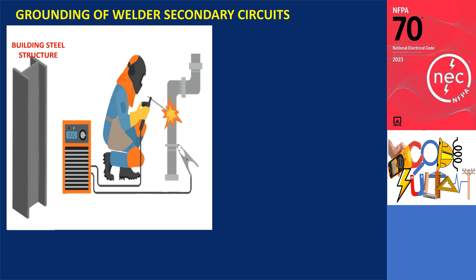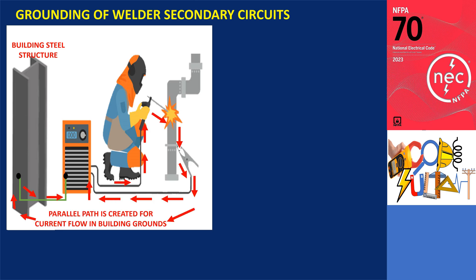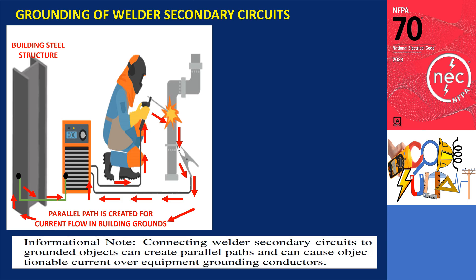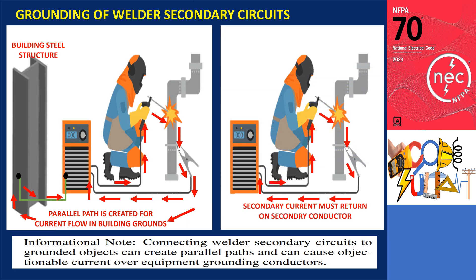Another situation where objectionable currents may arise is when the secondary circuits of a welder are connected to grounded objects. This connection can create parallel paths, resulting in objectionable currents flowing through equipment grounding conductors. This example is mentioned in the informational note of section 630.15, which pertains to the grounding of welder's secondary circuits. It is important to note that separately derived systems are not included in this scenario. To prevent objectionable currents, it is recommended to connect the workpiece terminal of the welder to the workpiece or workpiece table instead of the building's grounding system.